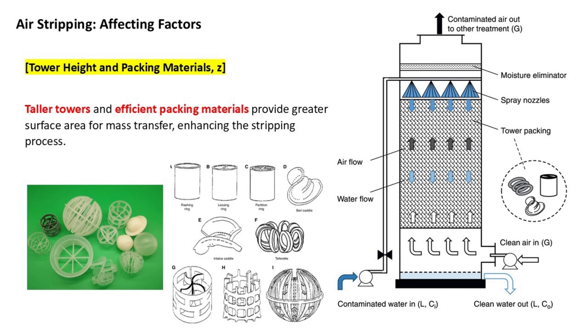Packing materials used in air stripping towers are generally categorized into two types: random packing and structured packing. Random packing consists of irregularly shaped pieces of material that are randomly dumped into the column. Common examples include pall rings, which are cylindrical rings with multiple openings to increase surface area and enhance liquid distribution; raschig rings, which are cylindrical hollow tubes that provide a moderate surface area for mass transfer; and saddle-shaped packing, curved pieces that reduce pressure drop while offering good surface area. These materials are cost-effective and easy to install, making them suitable for moderate flow rates and relatively simple applications. However, they can result in uneven distribution if not carefully managed, and may also clog over time in systems with high particulate loads.